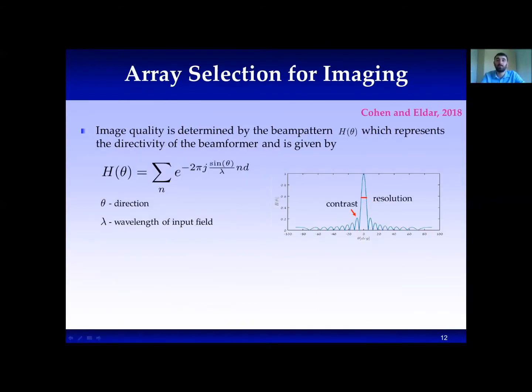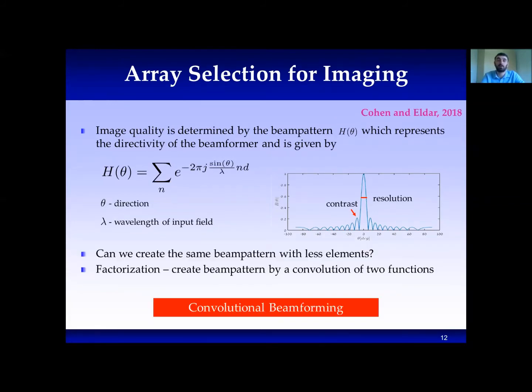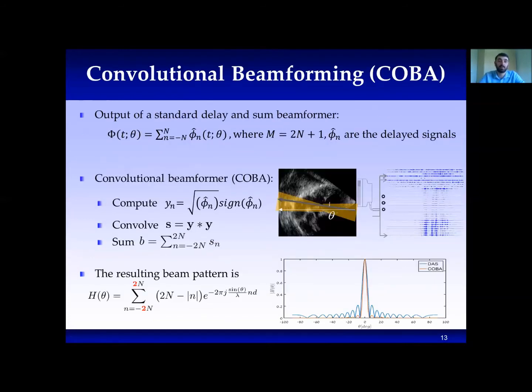Another method for image improvement while reducing data size is choosing a different array for imaging. The image quality is determined by the beam pattern's main lobe and side lobe amplitude. Cohen and Eldar introduced the Convolutional Beamforming Algorithm (COBA), which produces better images with fewer acquiring elements. In traditional delay and sum, delayed signals at each element are summed. In COBA, however, before summing the delayed signals, convolution over the spatial dimension is applied, resulting in an effective beam pattern with better resolution and contrast.